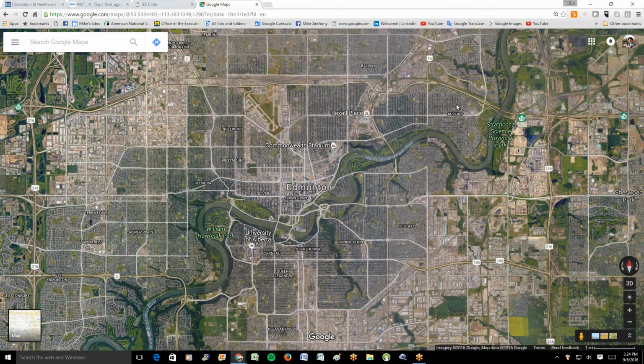Now, are you willing? Does it happen enough? That's the economic question we always have to address. In campus environments, and you're one of them, these power systems, a forced outage you couldn't plan for, will run $100,000 to $1 million a minute. If you get into research and you don't have an automatic main tie on your substations, you'll run up to $1 million a minute in losses. So it's playing the statistics, but I wanted to put those out there as two possible remedies. Maybe we can get one of the manufacturers to talk to us about that at some point, how you could more easily implement it.